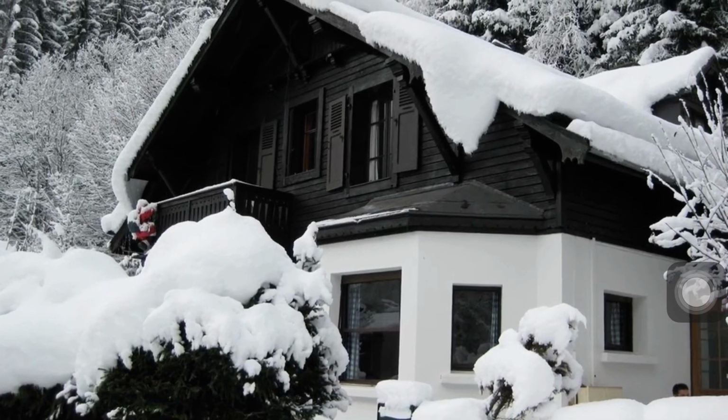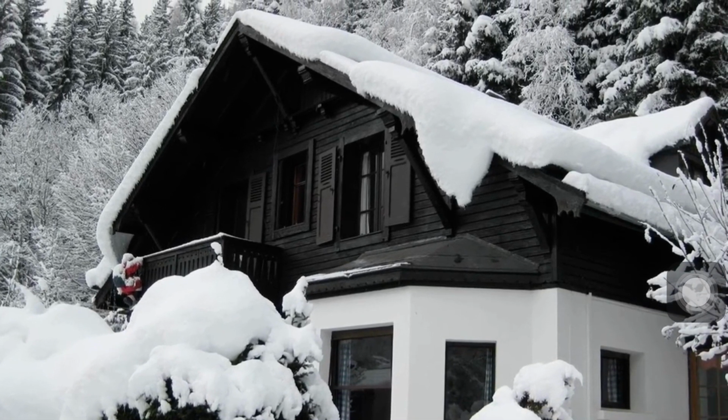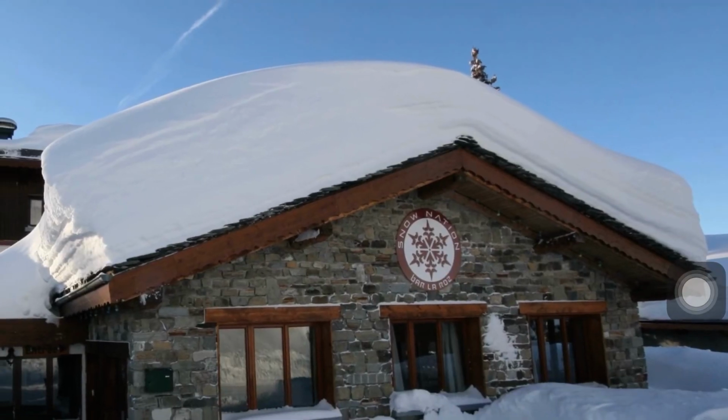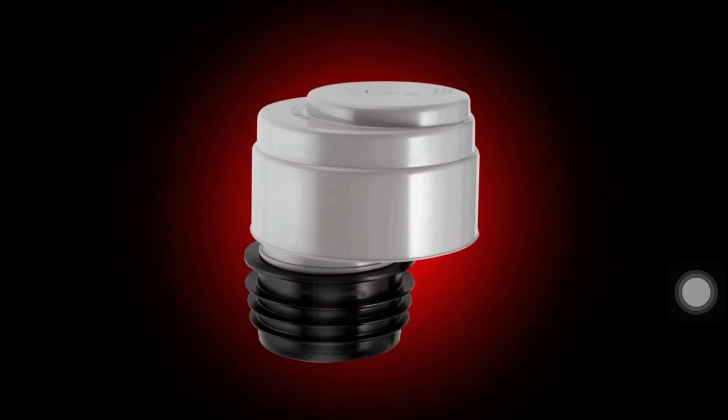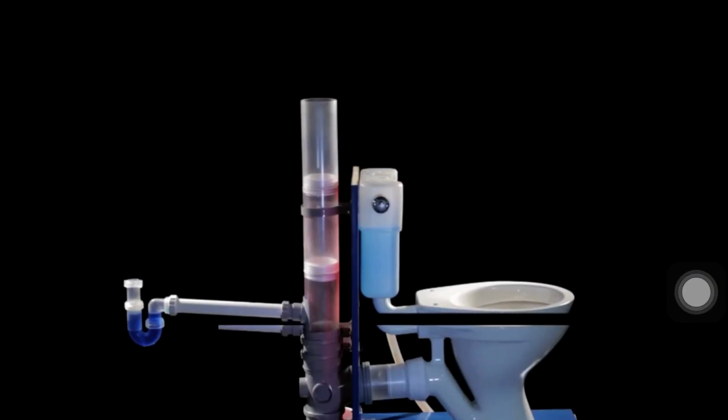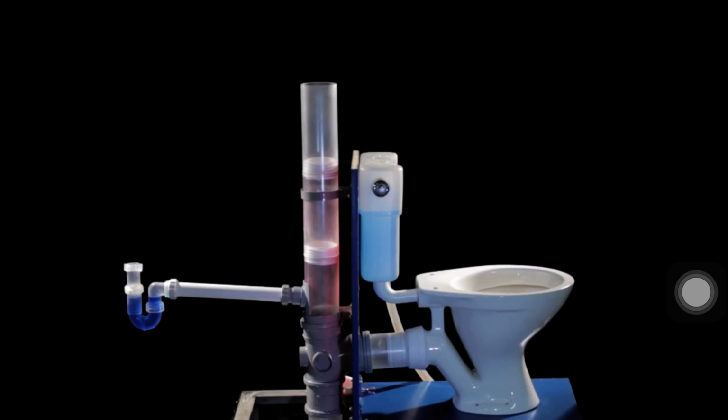One of the historical development reasons of the AAV was to remove the blockage risk created in the Scandinavian countries where large snowfalls covered the vent pipe. The need for ventilation can be illustrated with a simple test. Here, a WC and sink trap are connected to a vertical soil stack. The stack is open to atmosphere, simulating a through-roof vent.